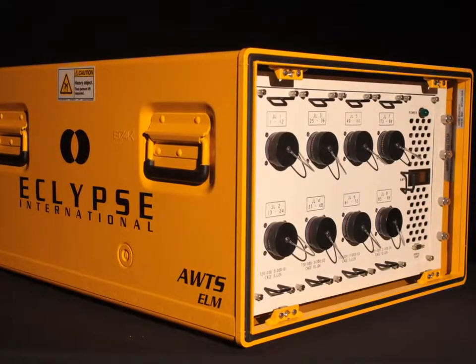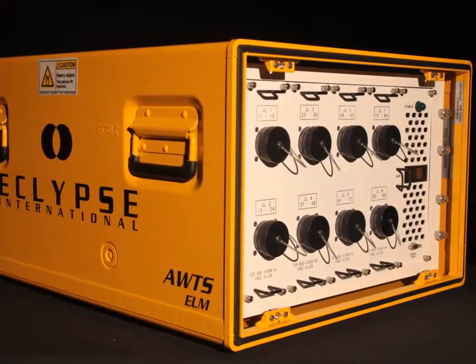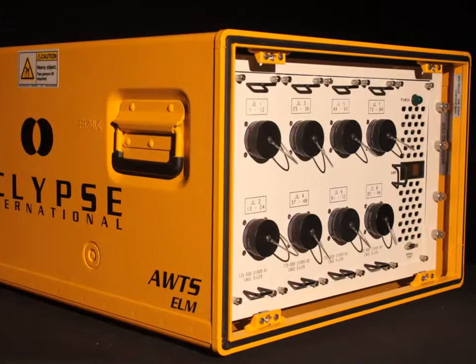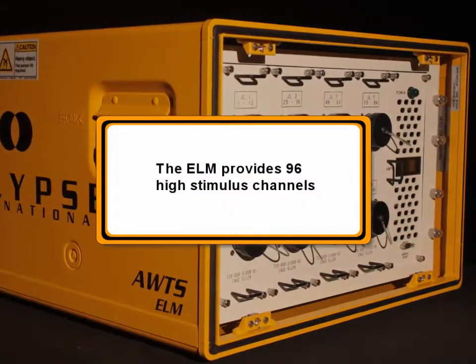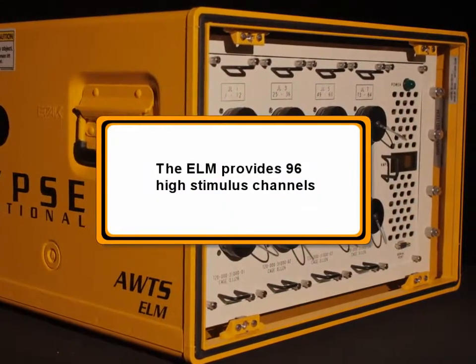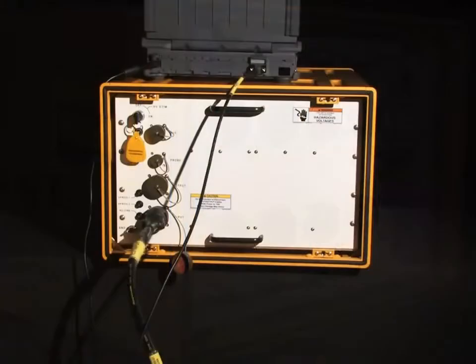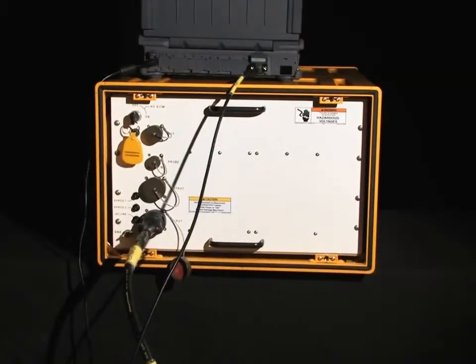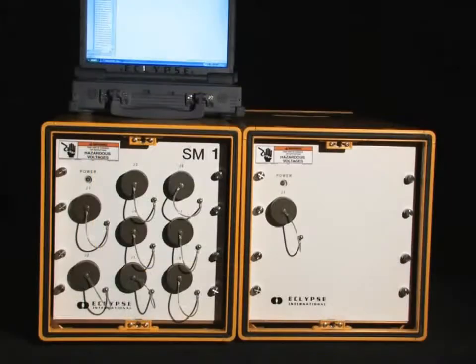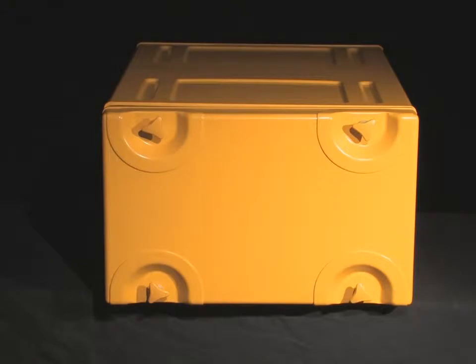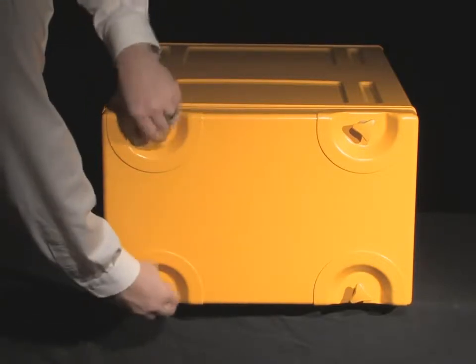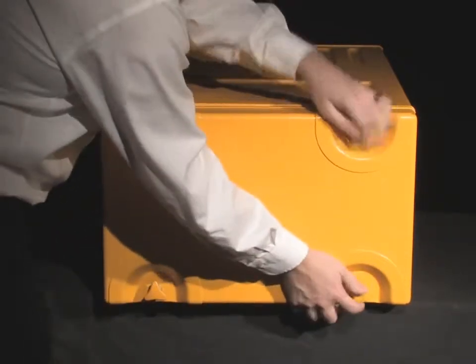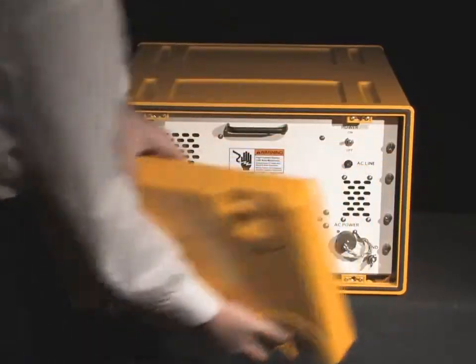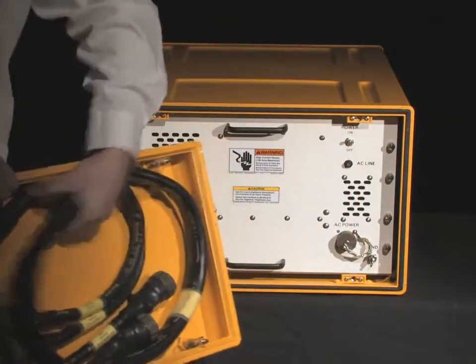The external load module unit is an ancillary piece of test equipment designed to attach to either AWTS configuration. It provides 96 high current stimulus channels. To attach an external load module to an AWTS system, first complete the basic AWTS system setup procedures. Then remove covers from the external load module unit by loosening the top and bottom fasteners of each cover. If cable assemblies are inside the covers for storage, remove them and set the system covers aside.